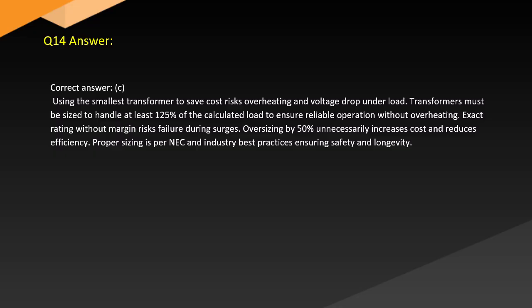Answer. Correct answer: C. Using the smallest transformer to save cost risks overheating and voltage drop under load. Transformers must be sized to handle at least 125% of the calculated load to ensure reliable operation without overheating. Exact rating without margin risks failure during surges. Oversizing by 50% unnecessarily increases cost and reduces efficiency. Proper sizing is per NEC and industry best practices, ensuring safety and longevity.